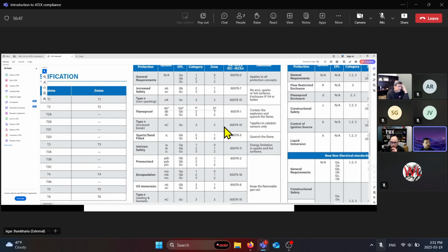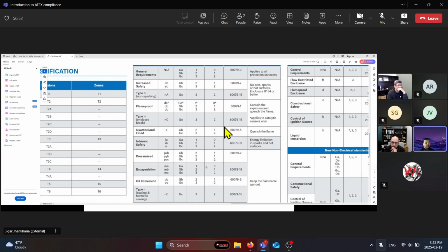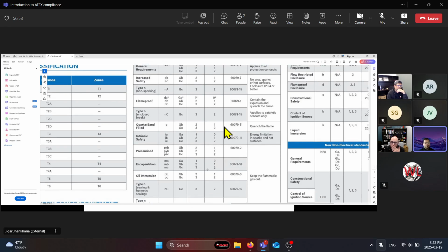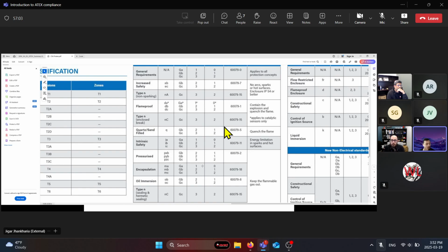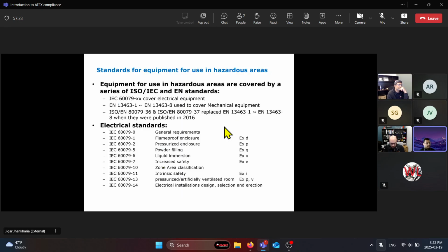Like I mentioned, DA, which is for zone 0, is only applicable to catalytic sensors. And encapsulation, you can achieve zone 0. Those are the only 3 methods of protection to achieve zone 0. Nothing else. So in your case, if you're looking at zone 1, increased safety is one of them. And I think you mentioned, Ray, in your email, zone 1 and zone 21 as well. Yeah, zone 1, zone 2, zone 21, zone 22. Okay, let's finish these gases ones, and then I'll get into the zone 20, 21, 22 requirements.